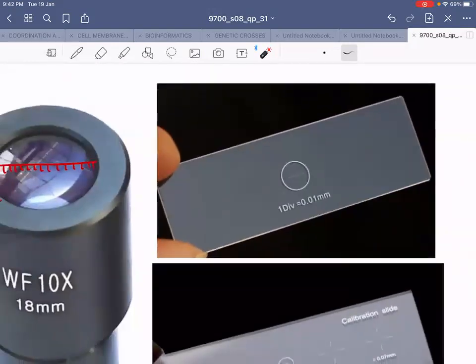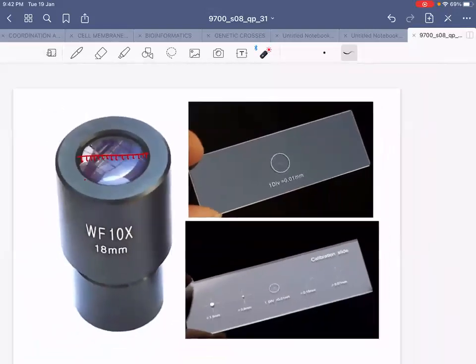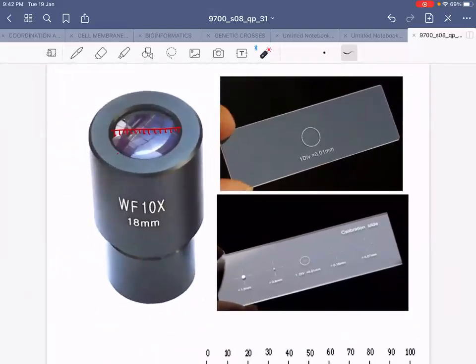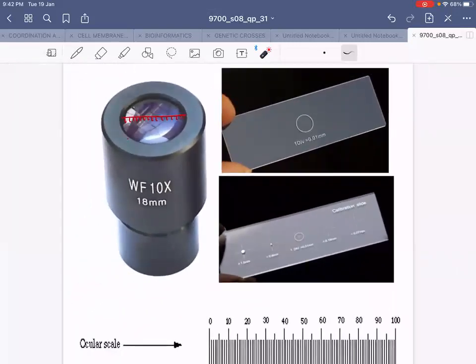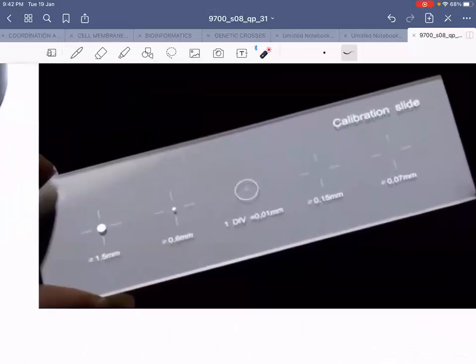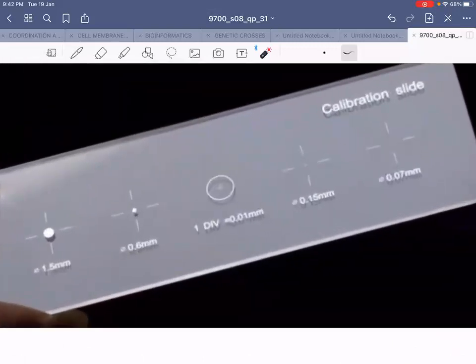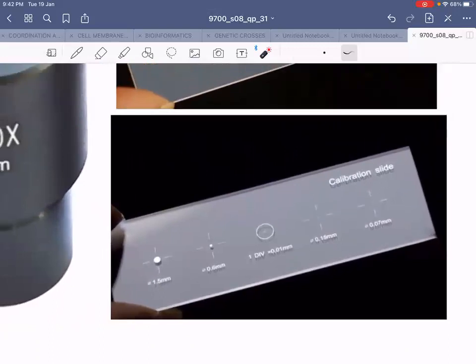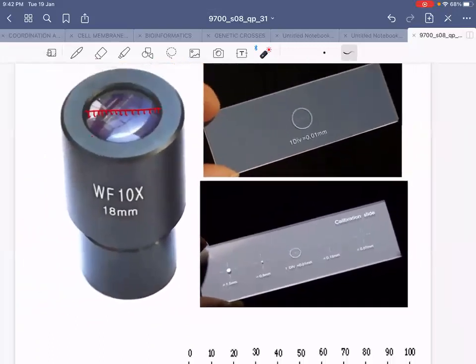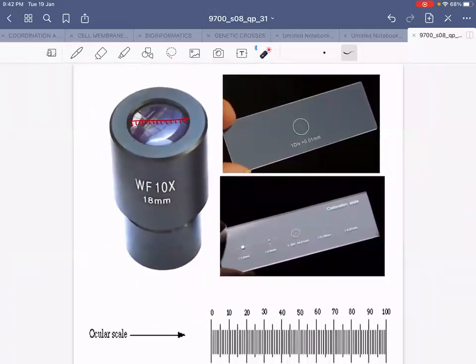Different laboratories have different stage micrometers — the smallest division might be as small as 0.01 mm, or 0.1 mm, or sometimes 1.5 mm or 0.07 mm and so on. The most common stage micrometer we use in our laboratory is the one in which the smallest division is 0.1 mm. So we'll be using that one.